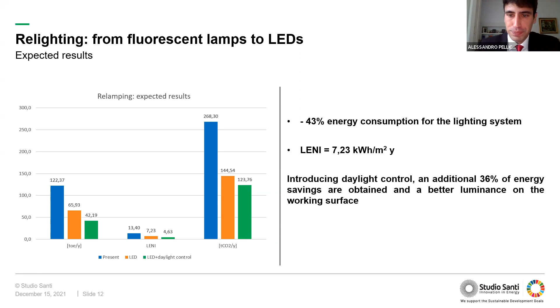And also more reduction will be obtained by implementing a daylight control system, consisting in dimming the light emitted by the lamps according to the sunlight which enters inside the building. We can see here that almost 43% will almost halve the consumption due to the light system, and even more, it will become a third if the daylight control system is also installed. And also the lighting energy numeric index will pass from 13.4 to 4.63 kilowatt hours per square meter per year, considering obviously also the light control system.